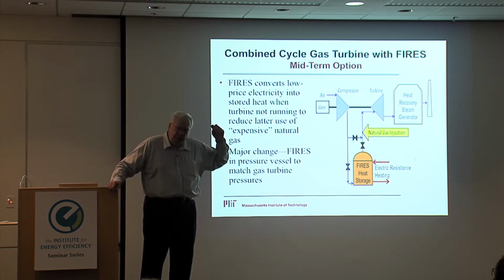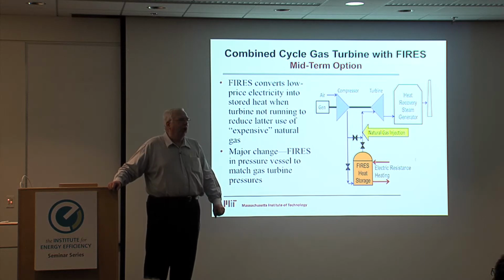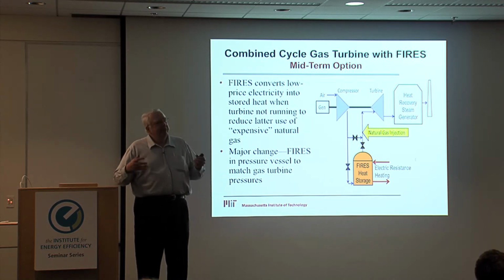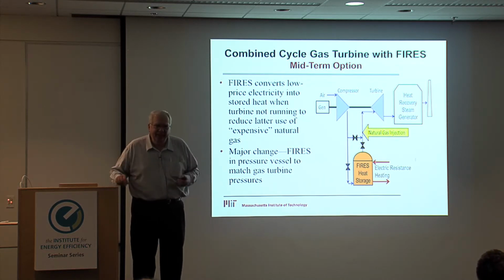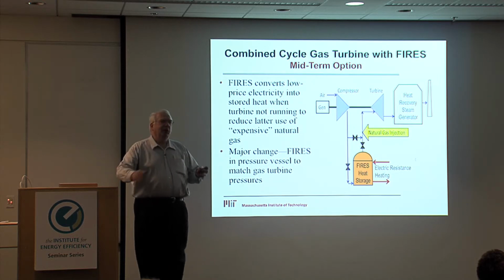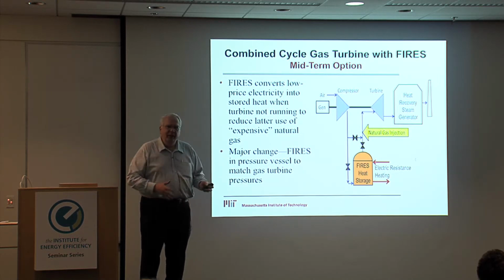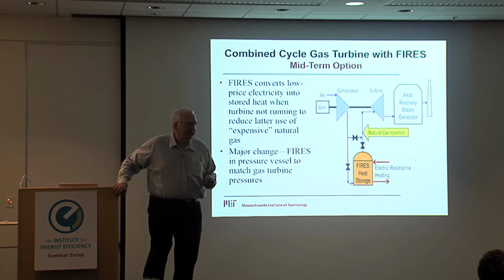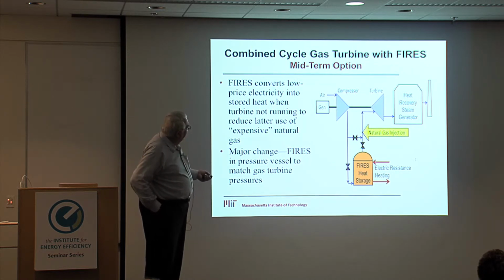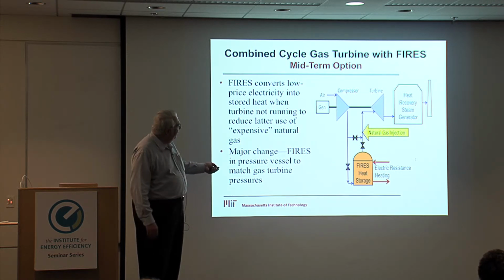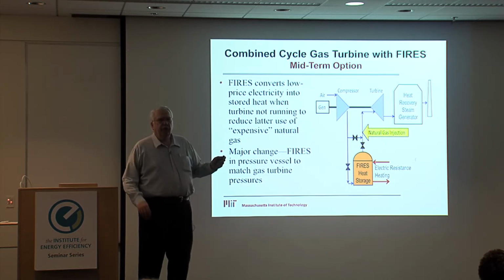We should be able to go at least 40,000 hours before an overhaul. So as a consequence, utility turbines always run a couple hundred C lower than the US Air Force. Now, you can see where we're heading - in a couple of years, certainly within 6 or 7 years, to 1600C.